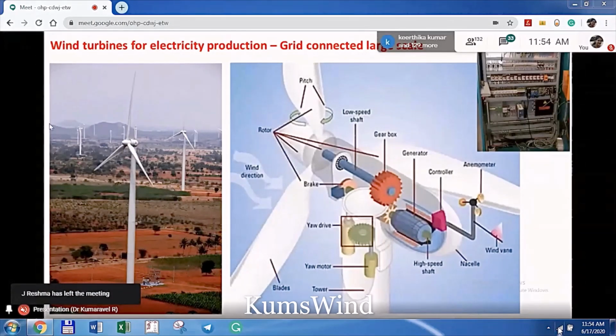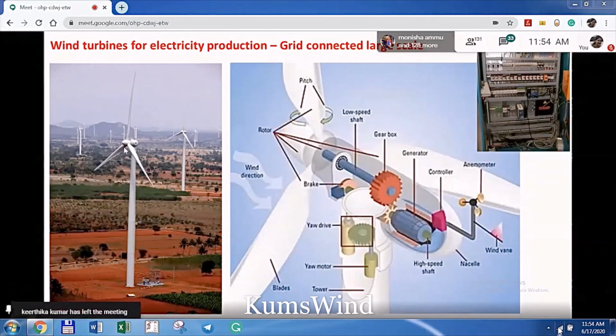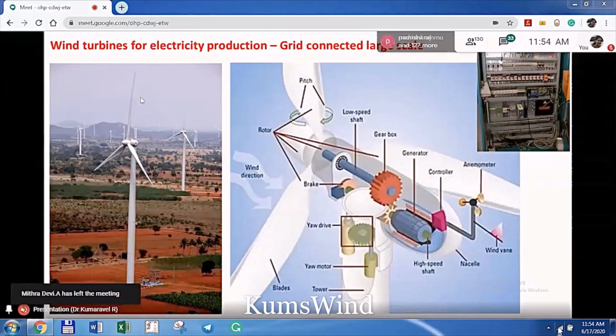But the only thing is, it should continuously have the wind speed it needs, which we call 14 meters per second, typically the rated wind speed for most turbines. If there is low wind, it will not produce the full rated power of 1.5 megawatt or 1,500 kilowatt. It will produce only less power, but when it gets 14 meters per second hitting the blades, then it will produce the rated power.